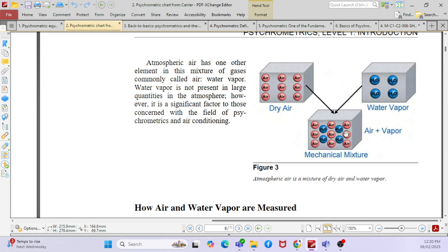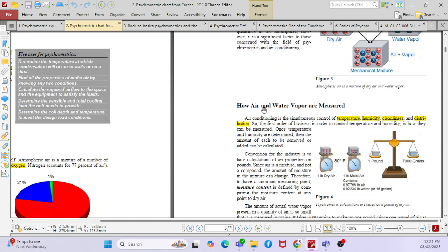So when you mix it, for example, if this is 20% or 10% RH, but to bring it to 50% RH, what will you do? You will add water vapor, right? That means you will do humidification, correct? So you will add a humidifier to spray water vapor in the air so that you can bring it to 50%. Assume that you have complete moisture, then you will add a heater to bring it to 50% RH.